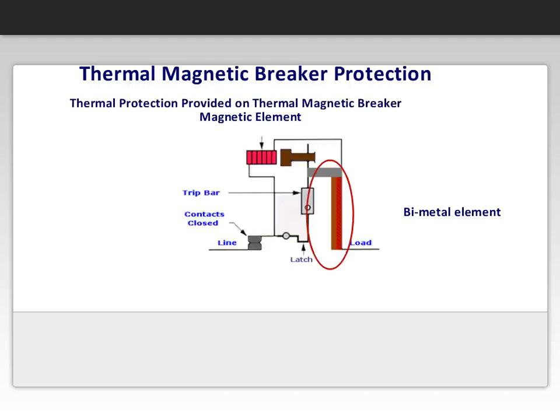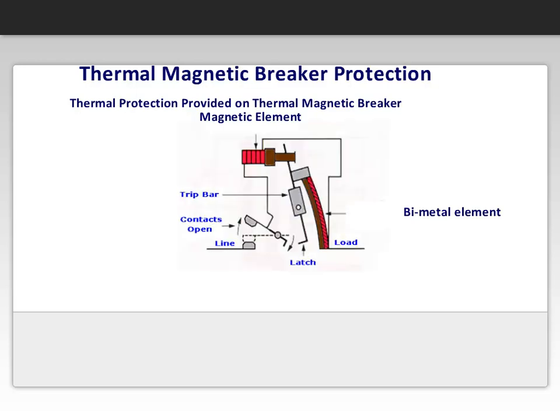The thermal overload protection functions in the same manner as a bimetal overload relay in a motor starter. It includes both bimetallic and magnetic elements. The standard thermal magnetic breaker includes the combined elements as shown in this diagram. You can see how the bimetal heating element is connected to the trip bar. If there's too much current in the system, the bimetal will heat and bend. At this point, the breaker contacts will open.